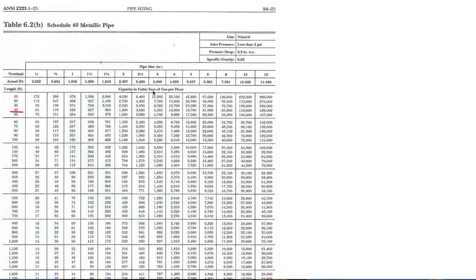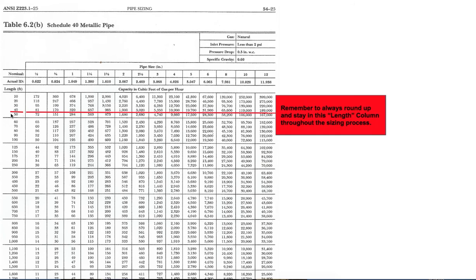However, you have to round up when you go to the chart. At the beginning the chart goes in increments of 10, so 36 is more than 30, which means you round up to 40. Again, this is the longest length method — this is the column used throughout the entirety of this sizing example.